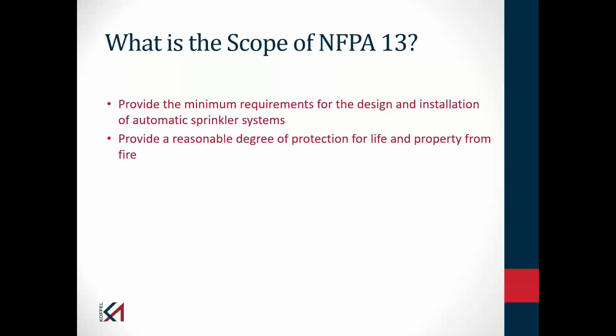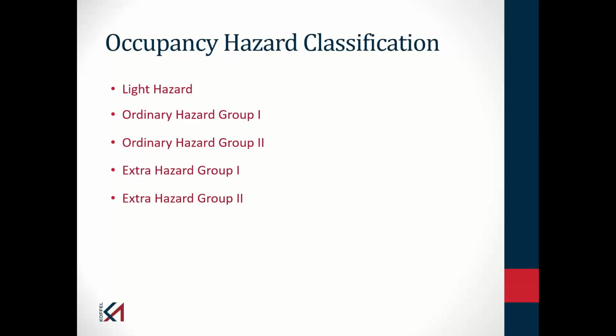And we have shown by fire tests and computer modeling that in residential occupancies, like your dorm rooms, in the patient sleeping room of a hospital, we can maintain tenability at the bed level from most fires in those types of occupancy. So there's the life safety benefit. And the fact that we're providing a life safety benefit obviously also then enhances the property protection. So let's talk a little bit about some of the design criteria. The way NFPA 13 operates is we have a series of boxes. And these are different than the boxes that you'll see in a building code or the life safety code, where you'll see references to low hazard, moderate hazard, and high hazard, because those tend to deal with the life safety threat of the fire. In the case of NFPA 13, we are dealing with the challenge the fire will present to the sprinkler system.